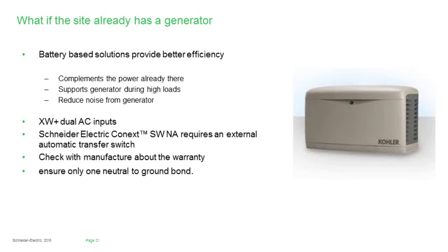One is that when we talk about the generator itself, make sure you do a little research and check that the manufacturer doesn't say that you can't use a generator as a charging source for batteries. I ran into that on a couple of different manufacturers, so double check the warranty if you are going to size it in, or if the generator's already there, make sure that the battery-based system is compatible for warranty purposes. And of course, we want to make sure that there's only one neutral-to-ground bond. Typically, the generator comes with a bond inside of it, and you'll need to remove that, because you can only have one ground bond inside the system. So just a few things to note.